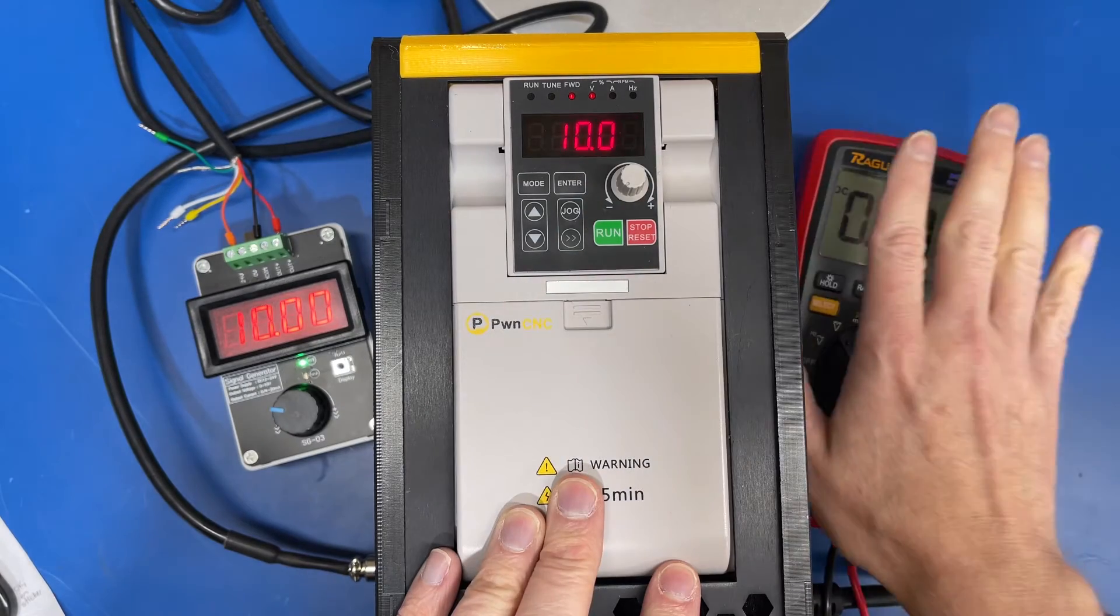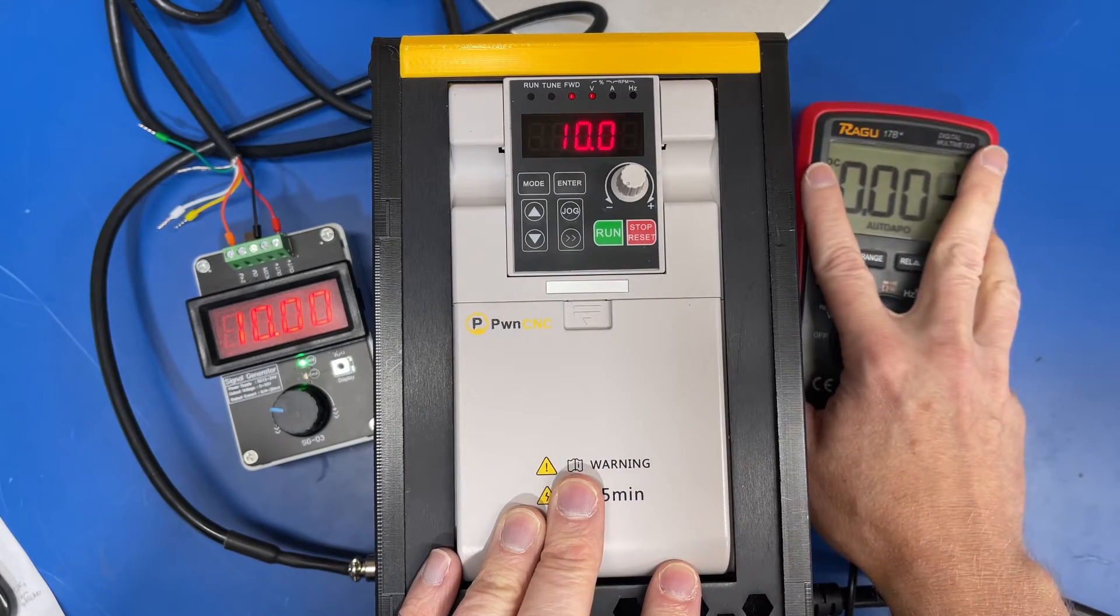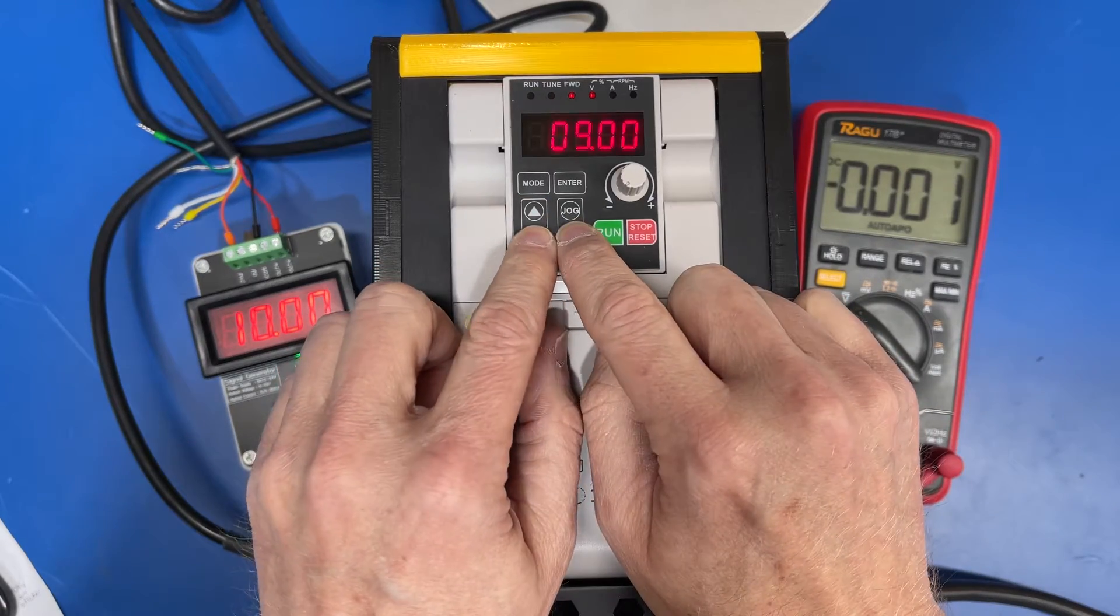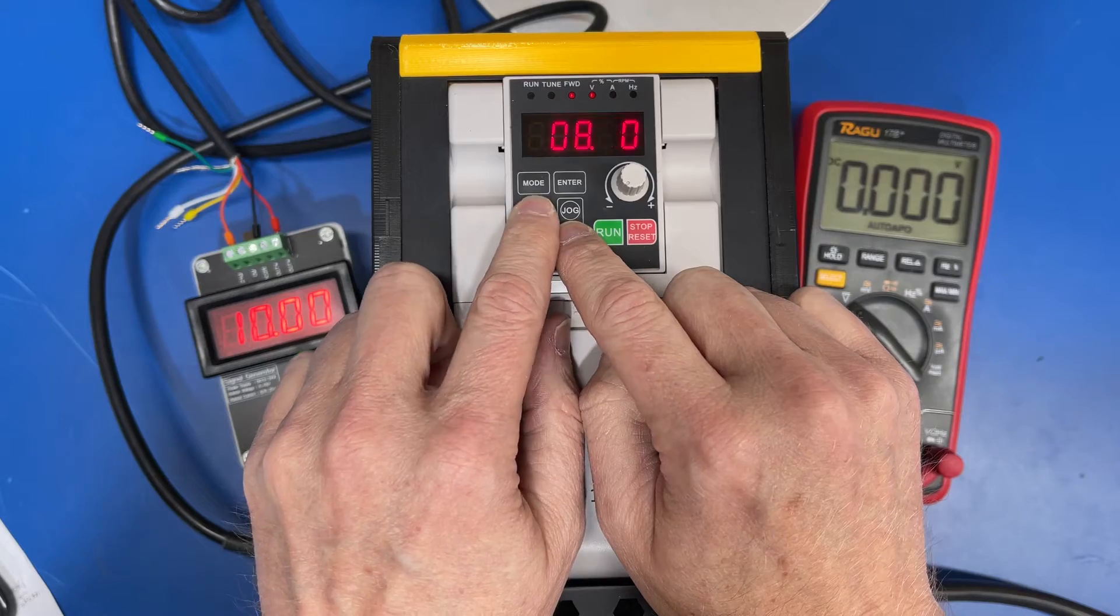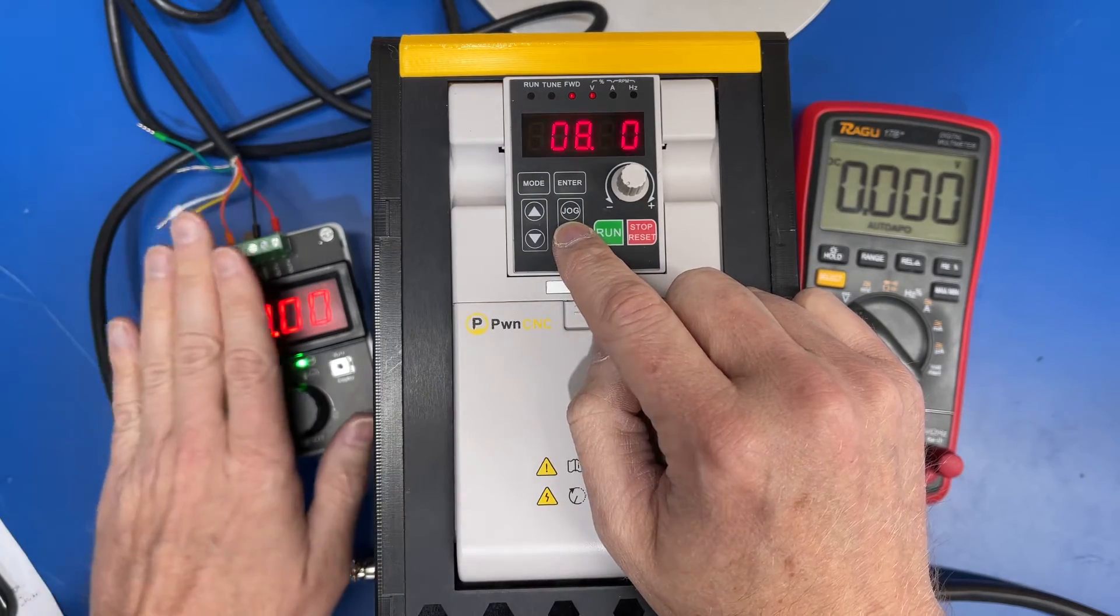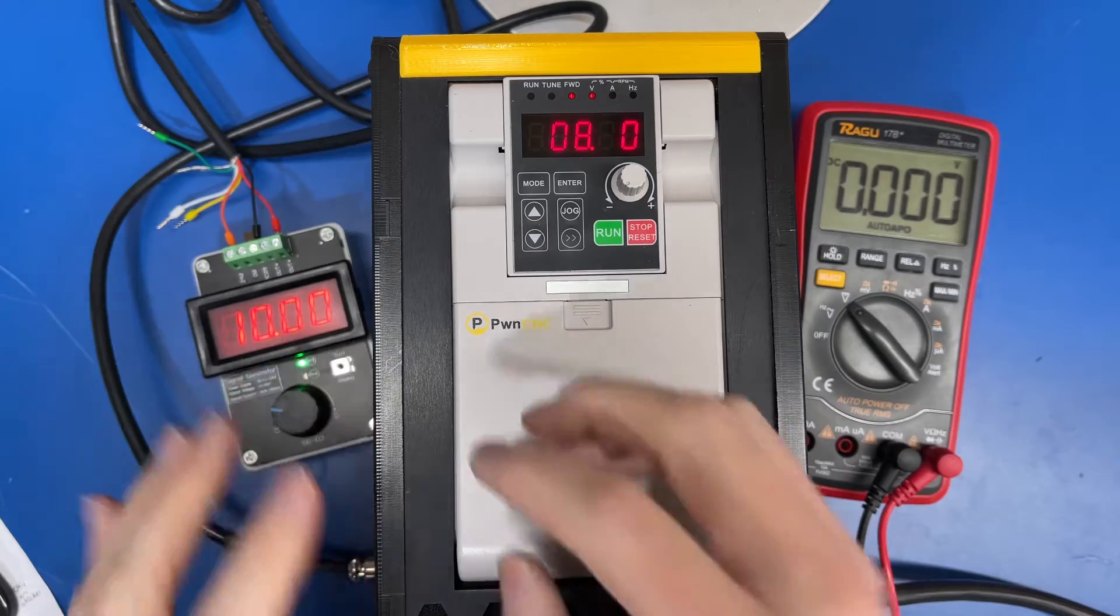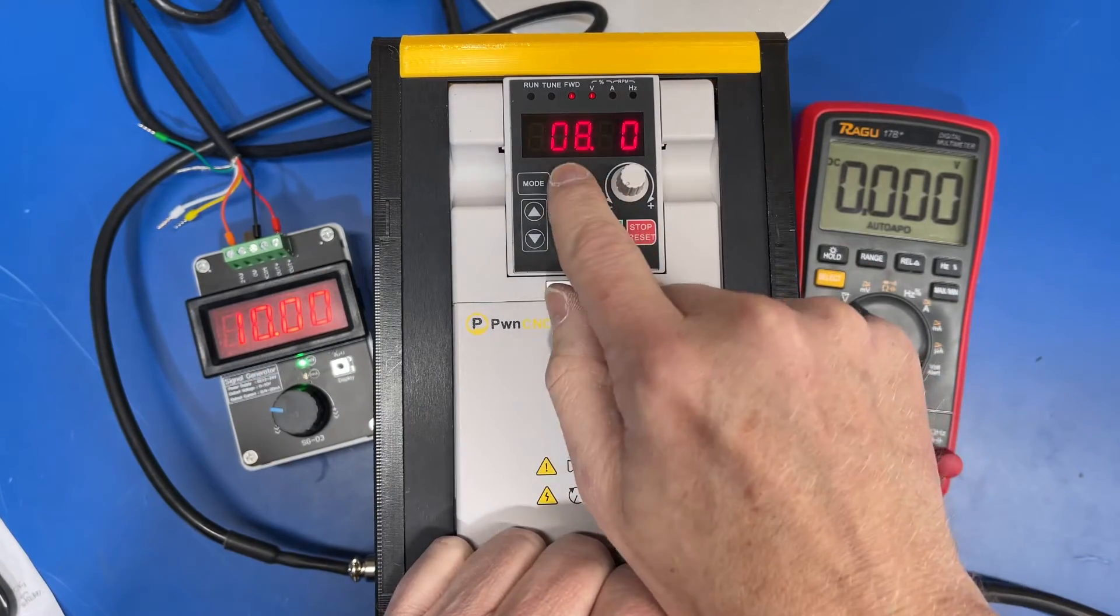Right now it's 10 volts. So we were seeing 8.4 volts as the maximum output. So let's adjust this down to 8.4 volts, since we know that's what our controller is able to output at the maximum speed. So if we hit save there, back out.